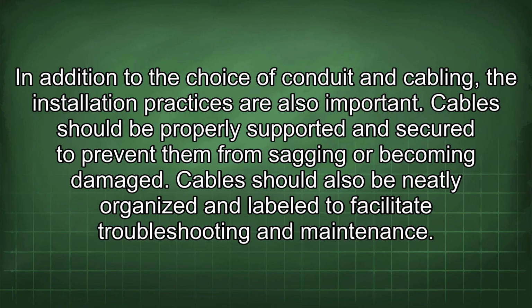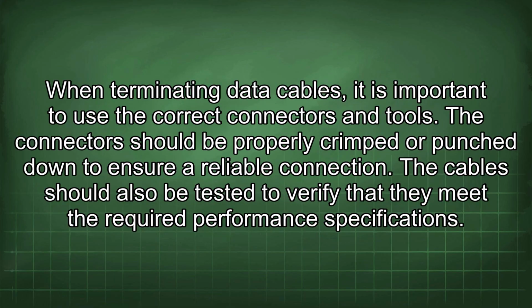In addition to the choice of conduit and cabling, the installation practices are also important. Cables should be properly supported and secured to prevent them from sagging or becoming damaged. Cables should also be neatly organized and labeled to facilitate troubleshooting and maintenance. When terminating data cables, it is important to use the correct connectors and tools. The connectors should be properly crimped or punched down to ensure a reliable connection. The cable should also be tested to verify that they meet the required performance specifications.